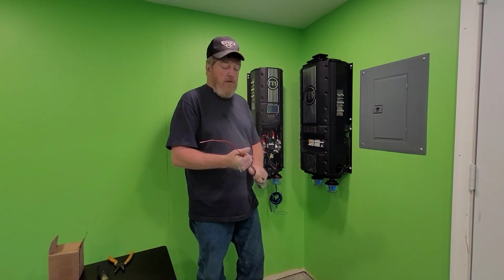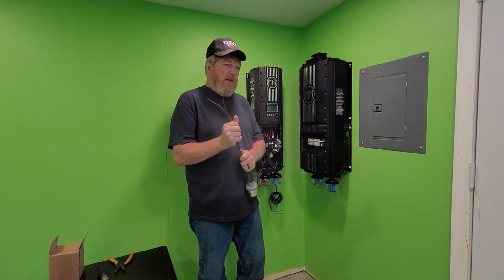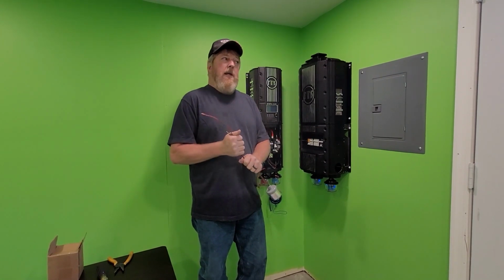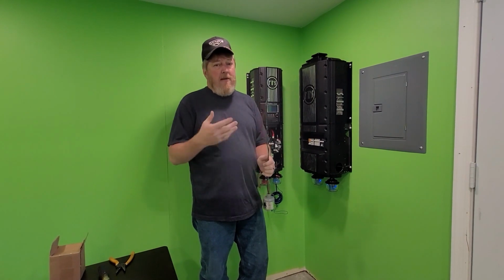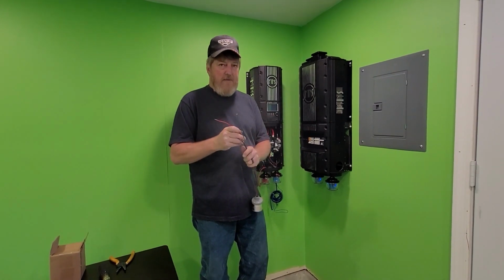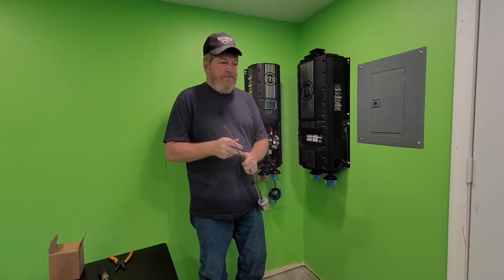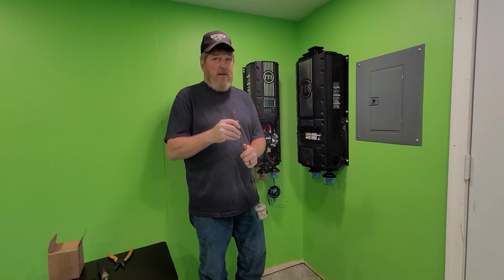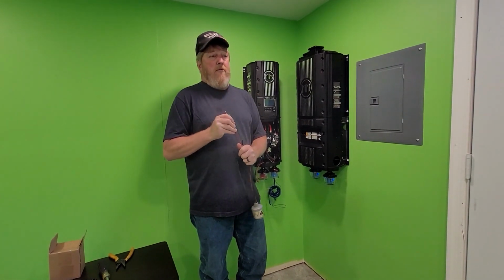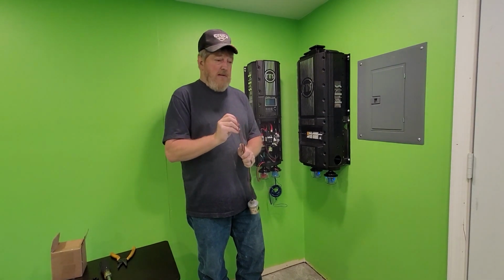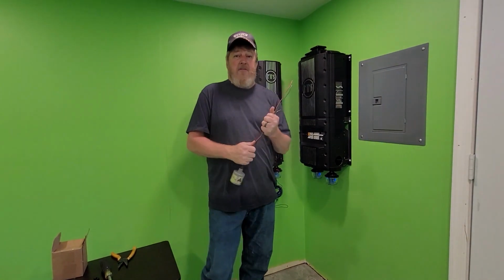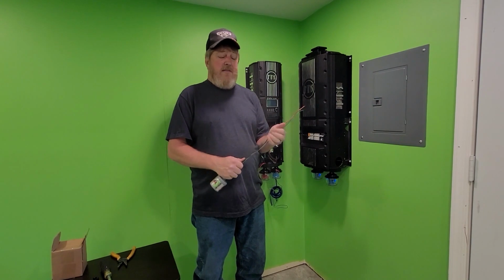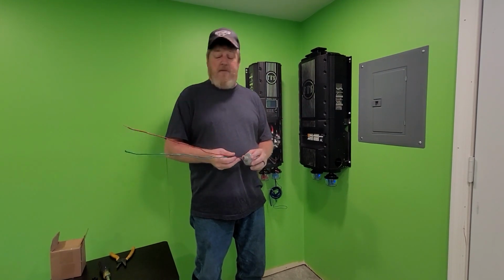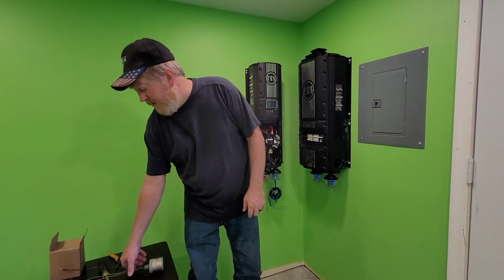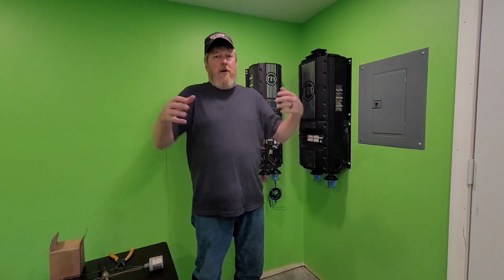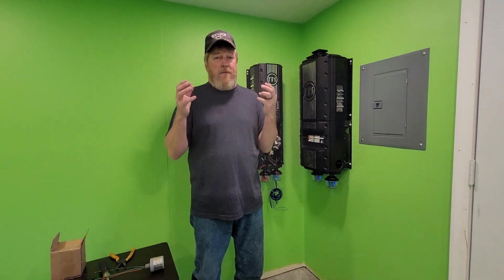So that's your goal, is to put an SPD wherever you think you've got something valuable. My general rule of thumb, and everybody has a different theory, is if you live in Florida where there's lightning everywhere, you may want to err more on the side of doing more than less. If you live somewhere there's never been a lightning storm in your life, maybe it's not quite as necessary. But my rule of thumb is to put one at every end of every wire that's longer than 50 feet and has anything worth protecting.